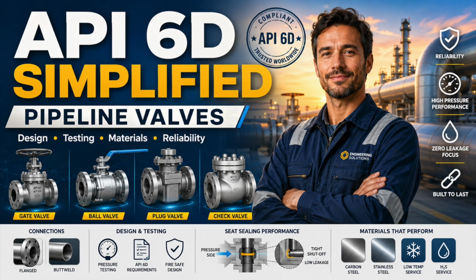Position indication is equally critical. A valve that appears open but is partially closed can obstruct a pig. A valve that appears closed but is not fully seated can defeat isolation. An actuator limit switch may prove actuator position without proving closure element position. For critical valves, mechanical indication, local indication, remote feedback, and diagnostic confirmation should be considered together. The more serious the consequence, the less you should depend on one indirect signal.